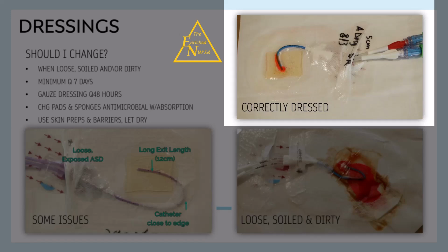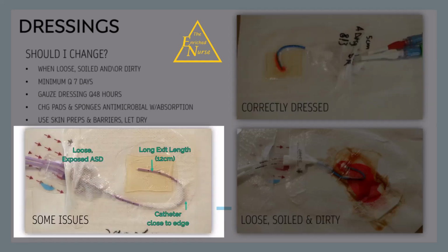The dressing on the bottom left side has a few potential issues. One, the catheter is close to the edge, so if that dressing peels up, the catheter will be exposed. Also, the exit length is pretty long. I would want to double check my insertion notes in the medical record if I saw a catheter that had this much length. That much length is going to be difficult to fully provide a good dressing coverage, so you may need to use an additional transparent membrane to provide good coverage. It's a good idea to make sure those securement devices are also covered with the dressing. I've seen those detach and come off the skin. If those things detach, then there's really not a whole lot of securement, and that dressing could become dislodged.